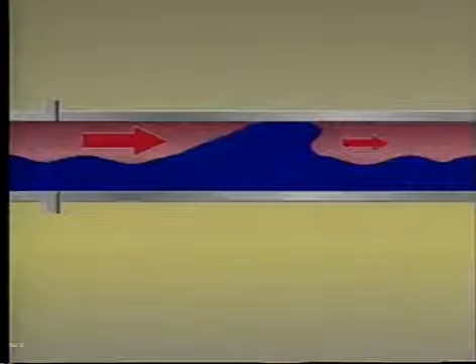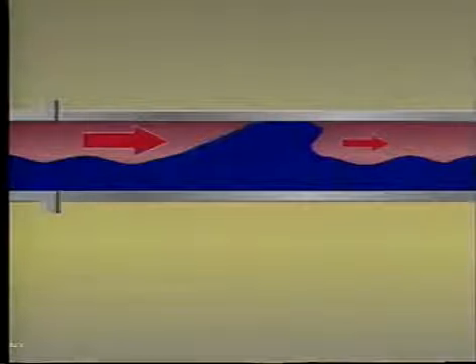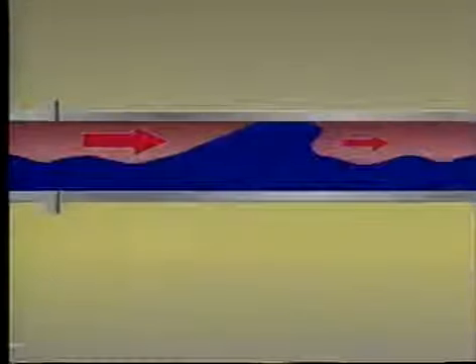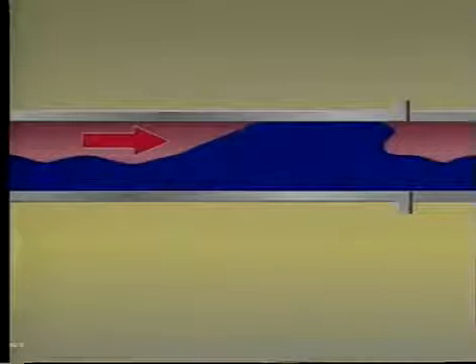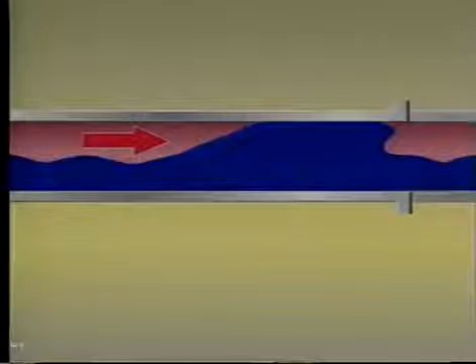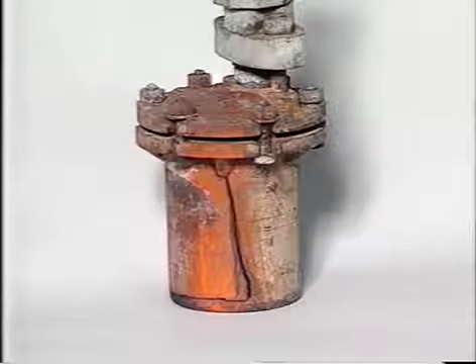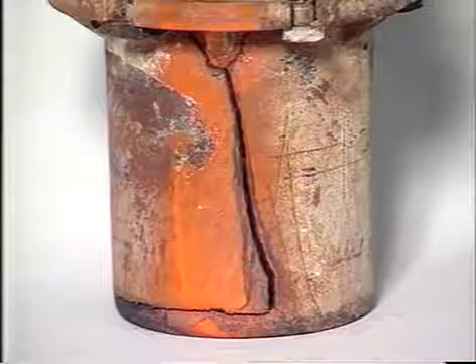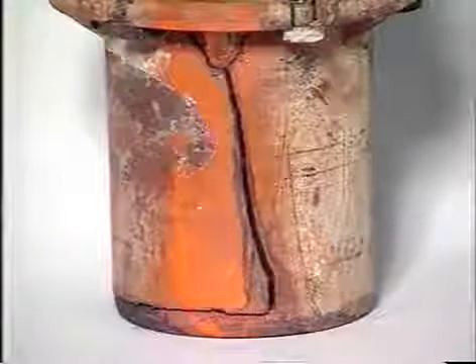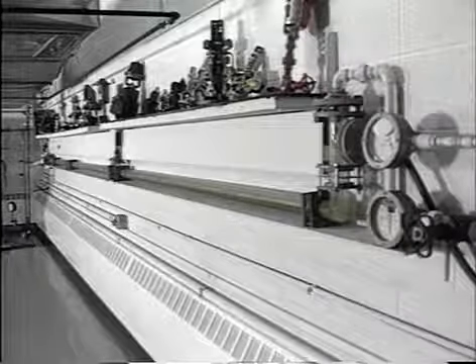Since the steam cannot flow through the condensate seal, pressure drops on the downstream side. The condensate seal now becomes a piston that is accelerated downstream by virtue of this pressure differential. As it is driven downstream, the piston picks up more liquid that is added to the existing mass of the slug, and velocity increases. This is differential shock. If the slug gains high enough momentum and is then required to change direction at a T or elbow, or is stopped by a valve, great damage can be done. In the demo lab at Armstrong International, we have assembled a fixture to illustrate the problem.